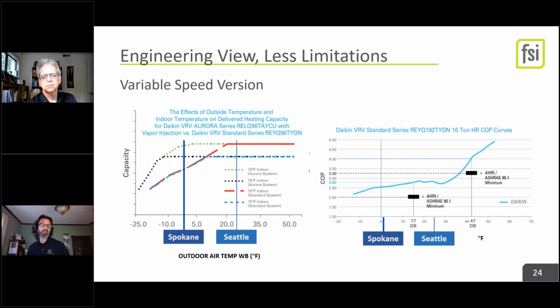I kind of agree if you're going to go out there and put a bunch of PTACs through your wall. Important note, you can also see the COPs are still quite good. So at a COP above 2 in Spokane or Seattle, you're still twice as good as electric resistance heating at those temperatures. So all in all, you're energy ahead for that heat pump. This would not have been true 5 years ago, is that right? It would not have been as good looking.